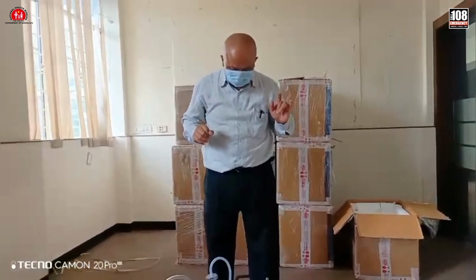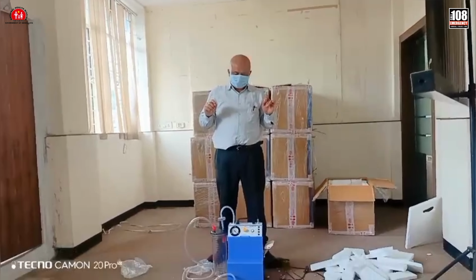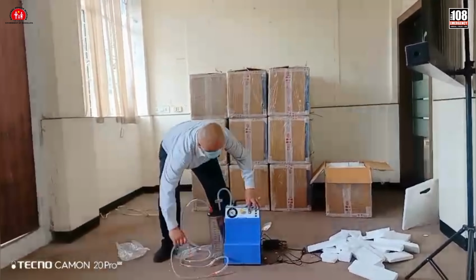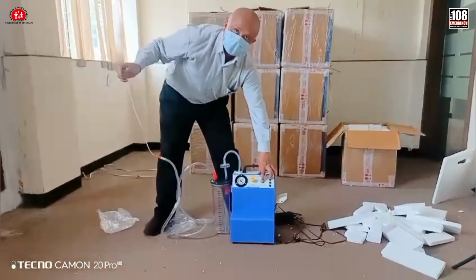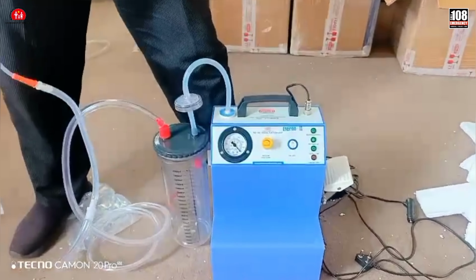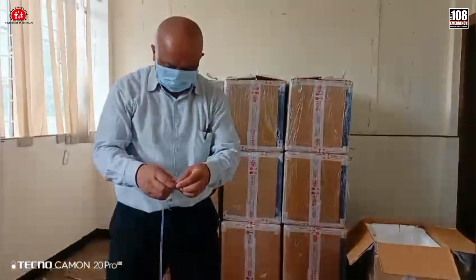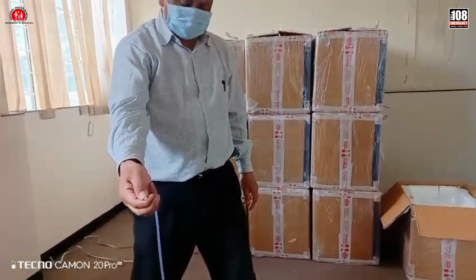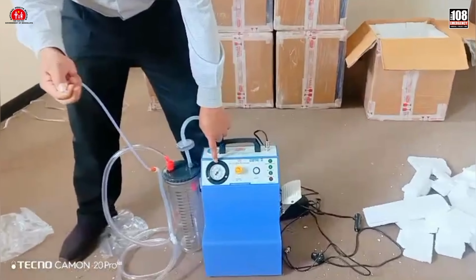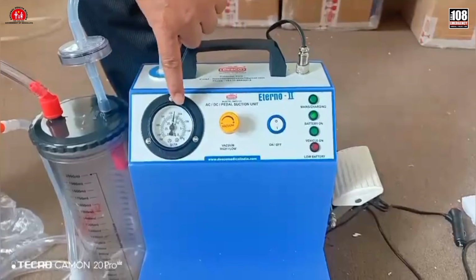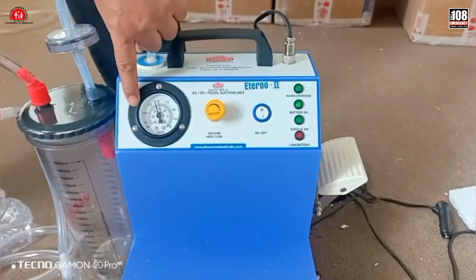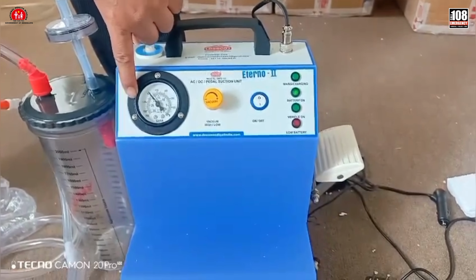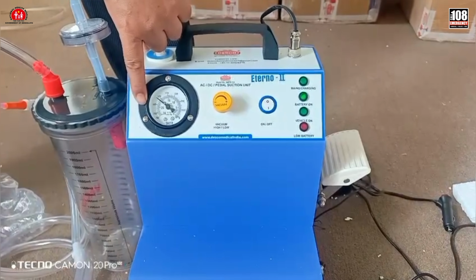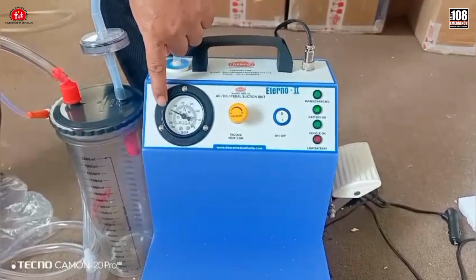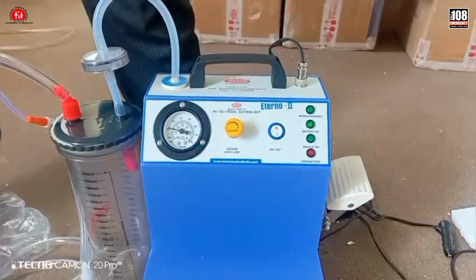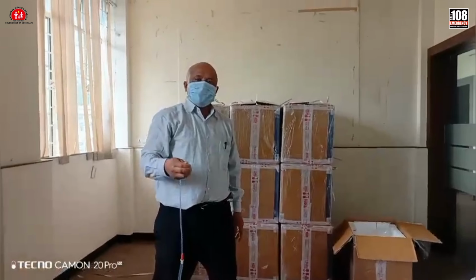Now, when you use this machine, all you have to do is put on this plug. Put on this switch here, and you can hear that sound. It means the machine is working. And then you can squeeze the end of a suction catheter like this, and you can see the pressure indicator. You can see this arm of the pressure gauge here, it rises up. This machine can give you a very decent supply of pressure. Usually the pressure that we need here is more than 500 millimeters of mercury. So you can use this pressure to do suctioning.